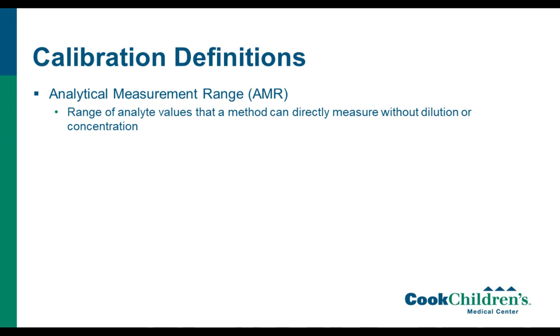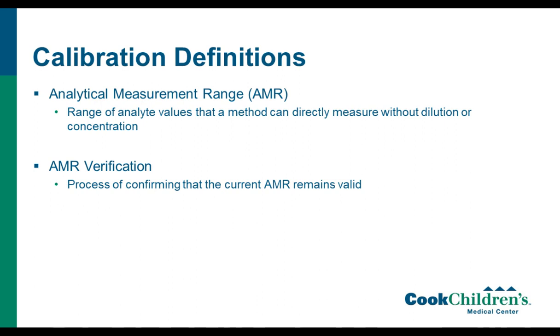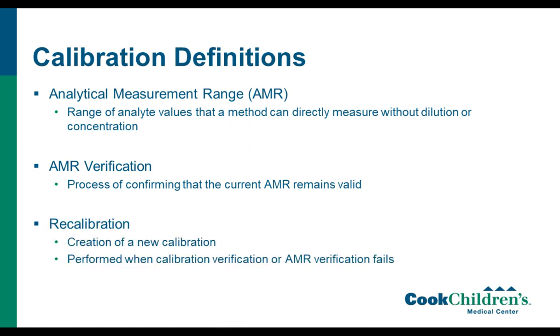There's also the analytical measurement range, or AMR, and this is the range of analyte values that a method can measure directly without dilution or concentration. So as the example I gave earlier, the assay going from 500 to 5 million IUs per mL, that would be the analytical measurement range. And so one of the QA requirements is to perform AMR verification, which is the process of confirming that your range remains valid. And then there's recalibration, which is basically where you're creating a new standard curve, following that initial calibration procedure we talked about. And this is performed when either your calibration verification or your AMR verification fails. Again, if you have an instrument where you have to create a standard curve each day of testing, these QA measures are not going to apply to you.